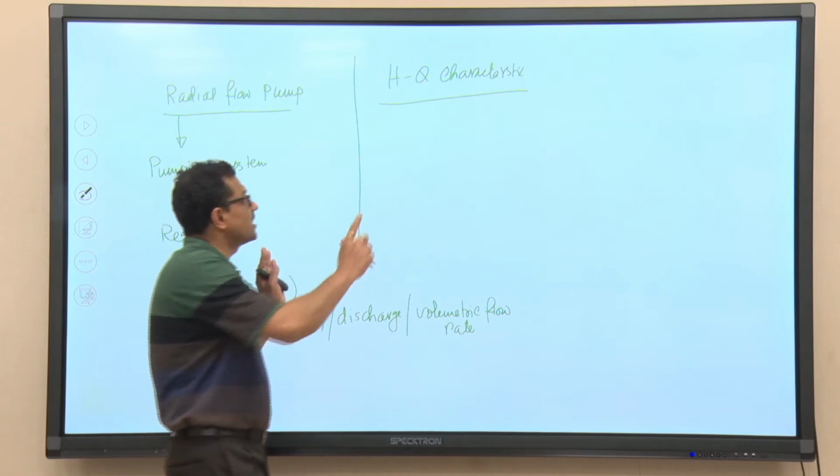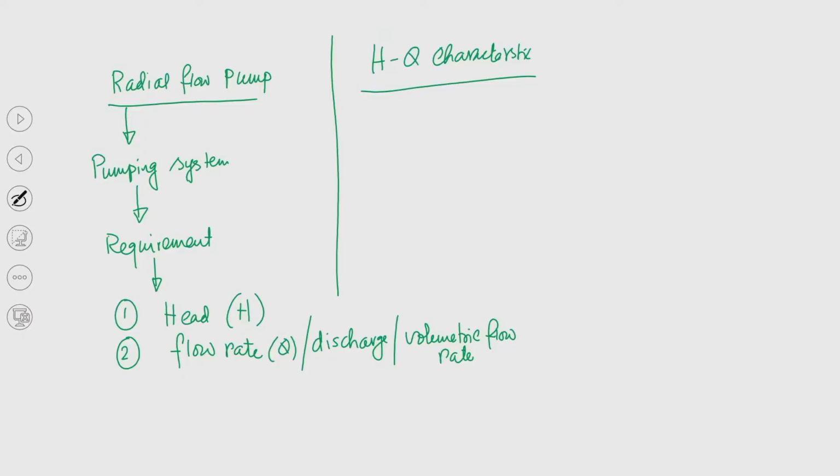So, the pump designer should provide this H-Q characteristic curve, that is very important. Looking at that H-Q characteristic curve, the supplier or system designer will check, for the system in which this pump should be installed, whether, experiencing that system resistance, the pump will be able to supply this amount of flow rate against the head H or not, right, and in that way the pump is selected.